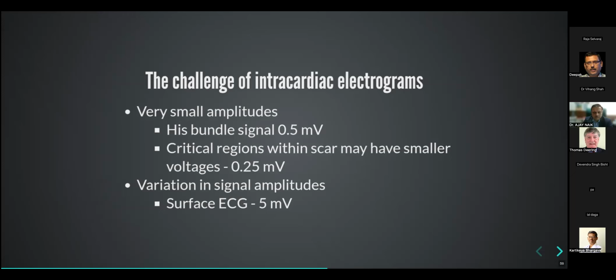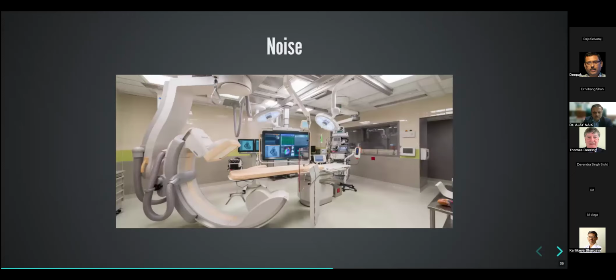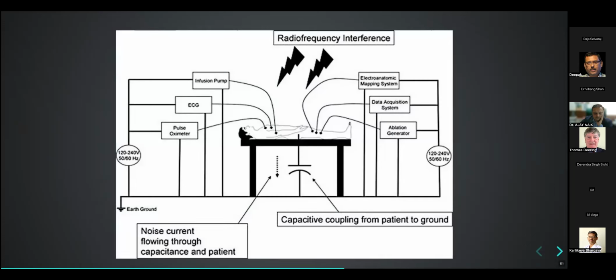And actually, the noise it sees is even much larger than this. In a typical cath lab, there are multiple sources of noise. Now, the cath lab, of course, is shielded for radiation, and that shielding itself also provides some amount of electromagnetic shielding, so outside noise doesn't come in. But inside the lab, you have a lot of electrical equipment. All these leak noise into the patient. So there are multiple sources of noise, and the system has to try and reduce all this noise.